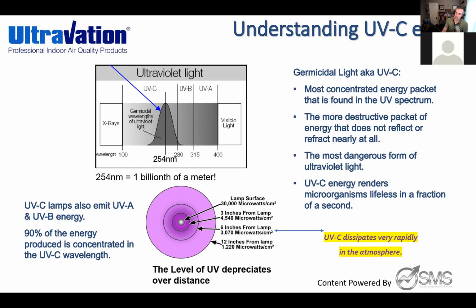As a reminder, this purple sphere at the very center is the tip of the bulb. So for people designing systems like the installs you've done, the closer to the surface of the bulb, the more potent and more dangerous it is. So most applications, you're going to look for proximity. So for coil, especially for surface, but even in airstream, you'd mentioned you've worked with our AS series in the past. You'll notice those bulbs are mounted 10 inches apart because we want to create some overlap of these UVC fields to create as much destructive energy in the air, in the ductwork, as air is moving by.